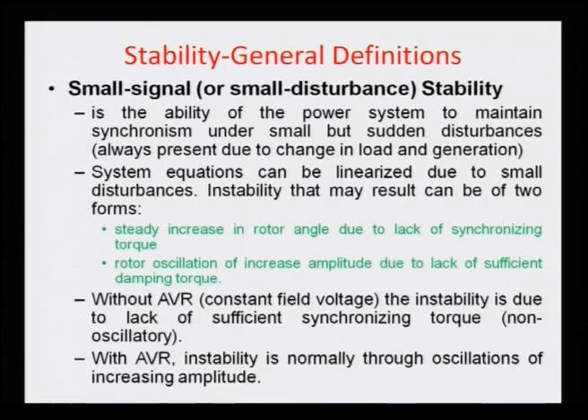But if you are using AVR, meaning automatic voltage regulation controlling the field voltage due to system disturbance, the instability is normally through oscillation of increasing amplitude, due to lack of sufficient damping torque. So without AVR it is especially due to synchronizing torque, and with AVR it is due to lack of sufficient damping torque.